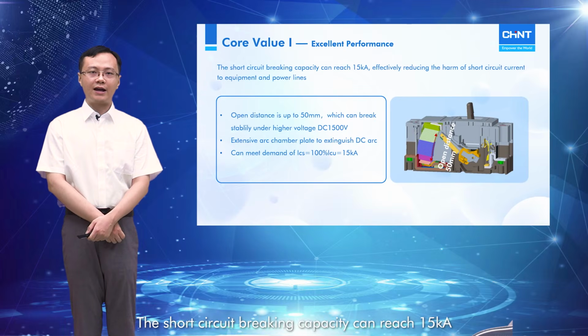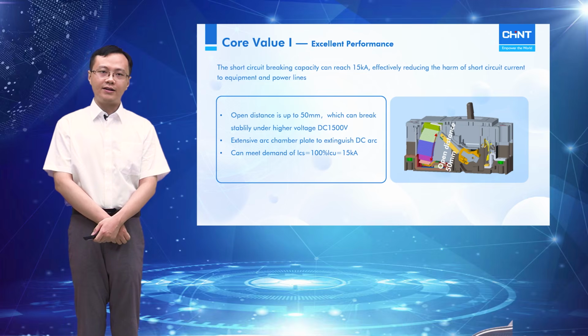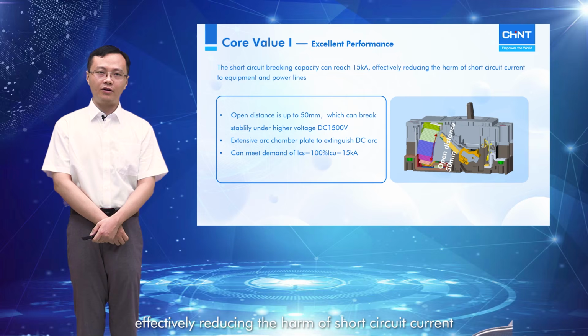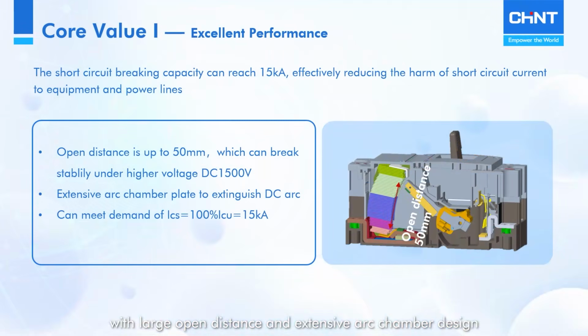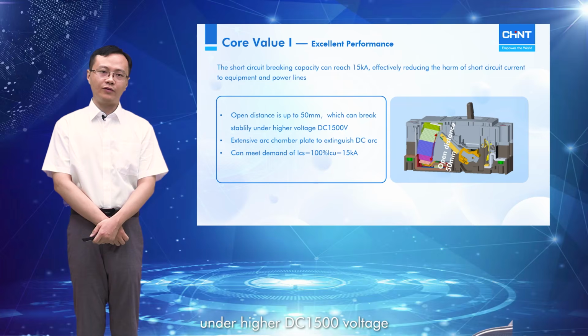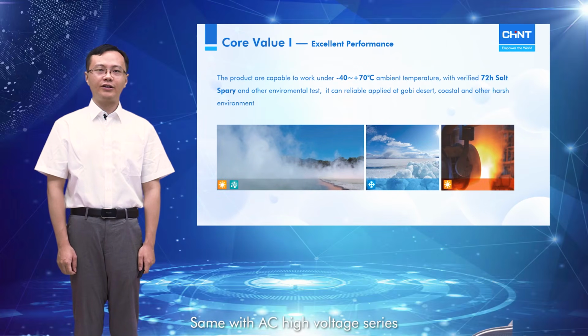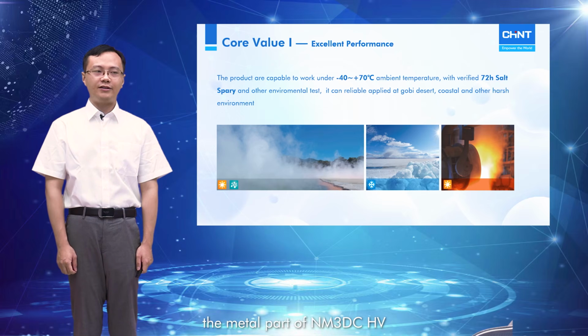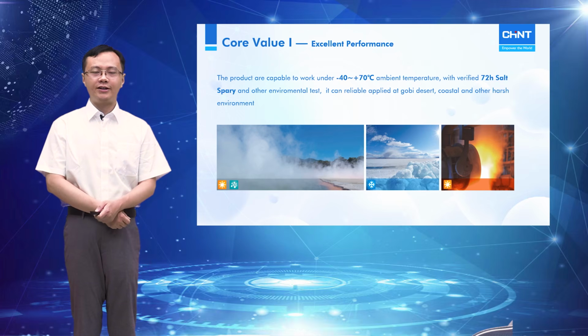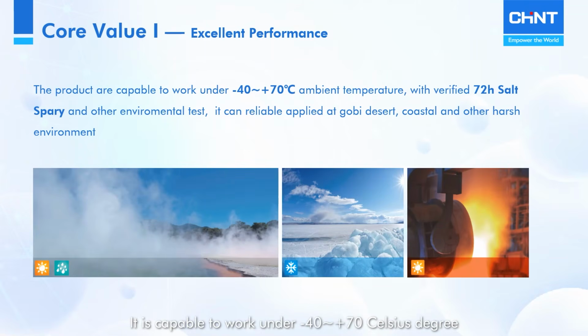The short circuit breaking capacity can reach up to 15 kA, effectively reducing the harm of short circuit current to equipment and power lines. With a large open distance and extensive arc chamber design, it is capable of breaking and making stably under higher DC 1500 volt. Same as the AC high voltage series, the metal parts of NM3DC HV are processed by a special technology. It is capable of working under -40 to +70 centigrade ambient temperature with verified 72-hour salt spray and other environmental tests. It can be reliably applied in the Gobi Desert, coastal areas, and other harsh environments.